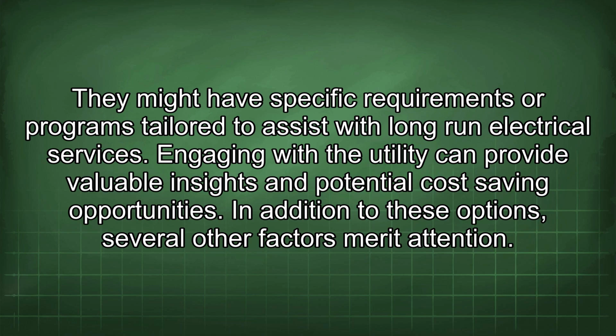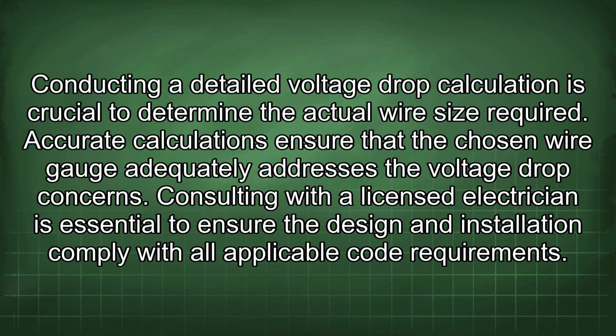In addition to these options, several other factors merit attention. Conducting a detailed voltage drop calculation is crucial to determine the actual wire size required. Accurate calculations ensure that the chosen wire gauge adequately addresses the voltage drop concerns.